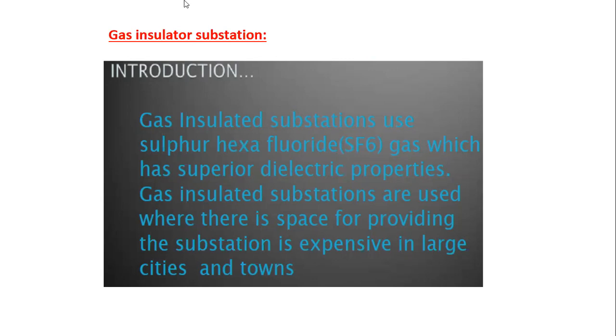These gas insulated substations are used where the space for providing the substation is expensive, where the space availability is very less. It is one of the major important criteria. If the space availability is more, we prefer an air insulated substation. But if the space availability is less, we prefer the gas insulated substation.